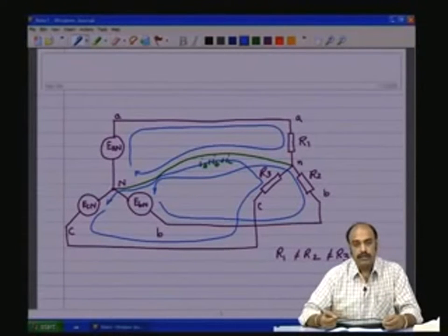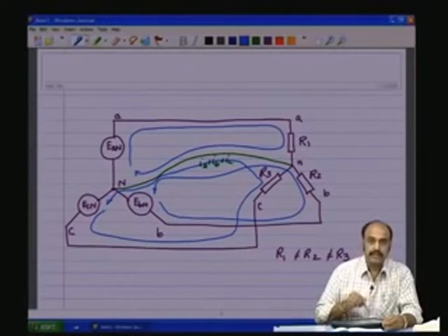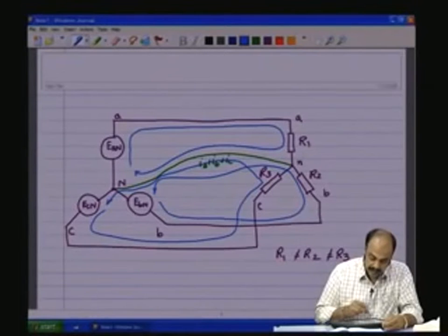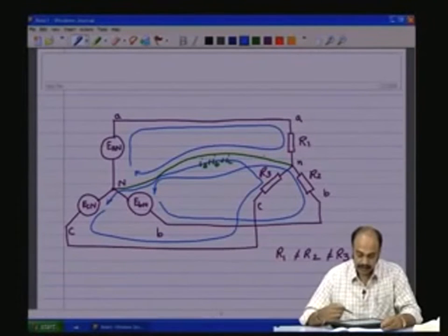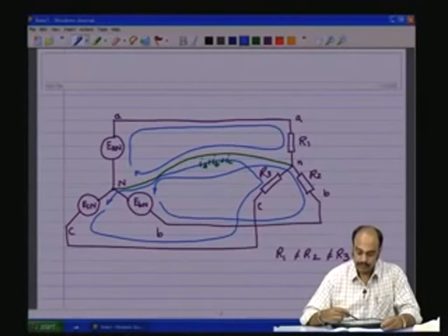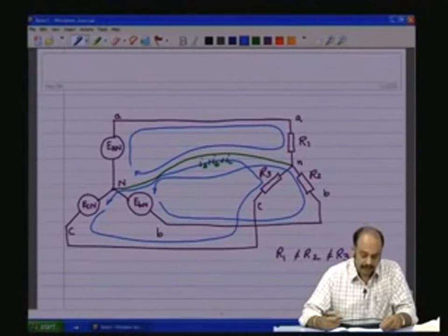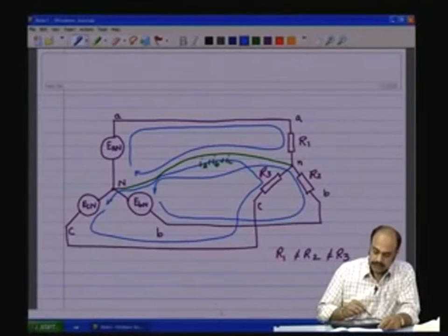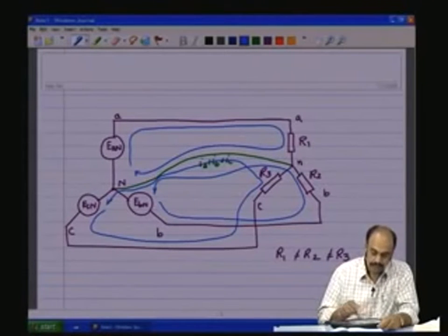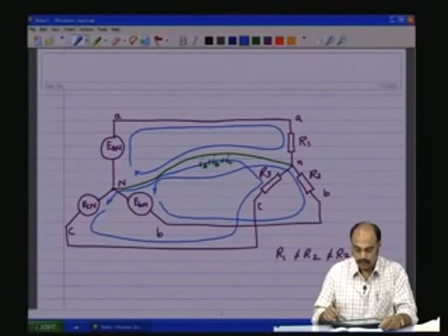The voltages across all the three phases will still be the same as decided by the source, whereas if this green line, the neutral connection, is not there, then the unbalanced currents will get mixed up and flow through the other loads, and then you can have voltage distortions. So, in a star, to take care of the unbalanced load, you would normally connect the neutral points.